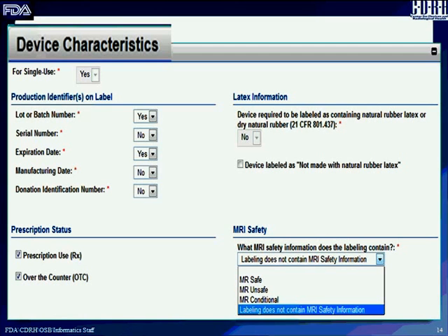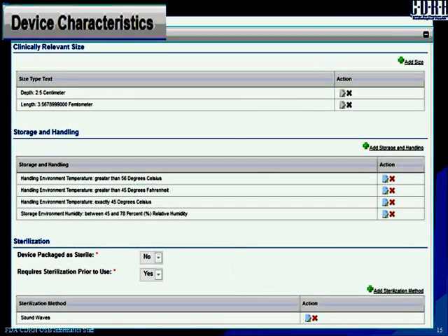So now time to get into the nitty-gritty about how the DI record works in the GUDID. So to start off, some key concepts. The new DI trigger attribute. This is extremely important to understand and manage on your end. We have several GUDID attributes, out of which we have chosen 11, and we call them the new DI trigger attributes. So what are these? These are attributes that when you change them, they no longer represent the same device. And we say, therefore, they require a new device identifier.